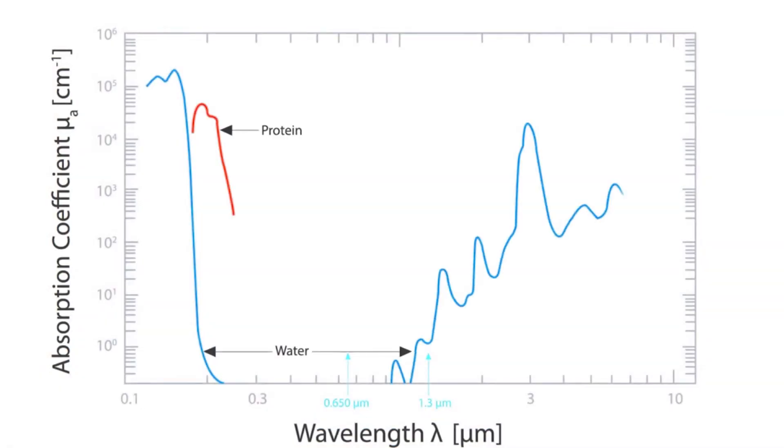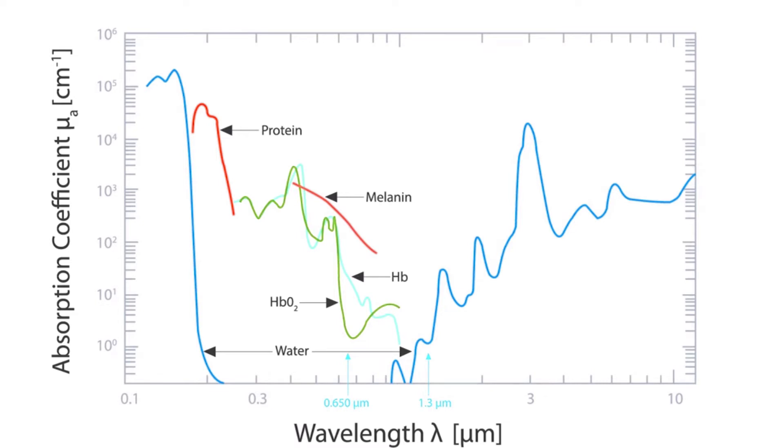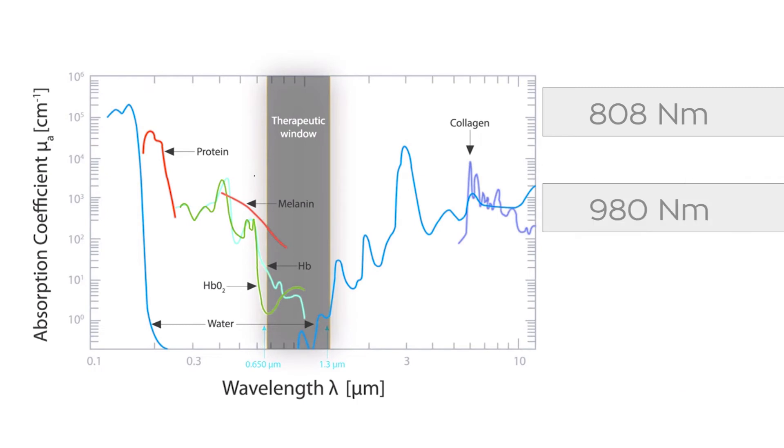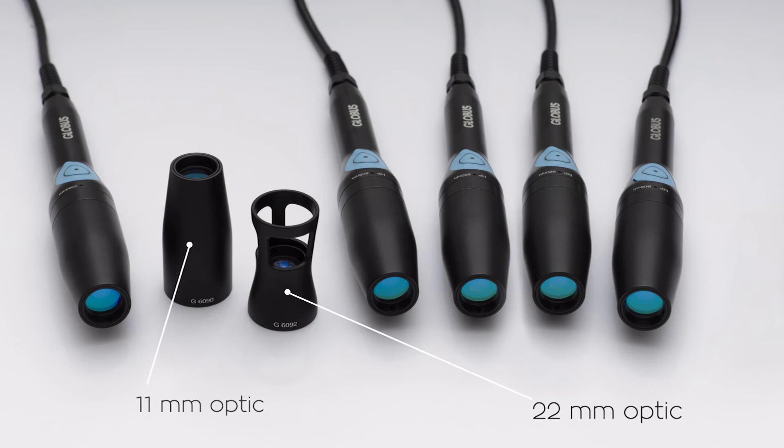The Globus laser devices can use three different wavelengths which fit into the so-called therapeutic window: 808, 980, and 1064 nanometers, with 11 or 22 millimeter diameter optics.